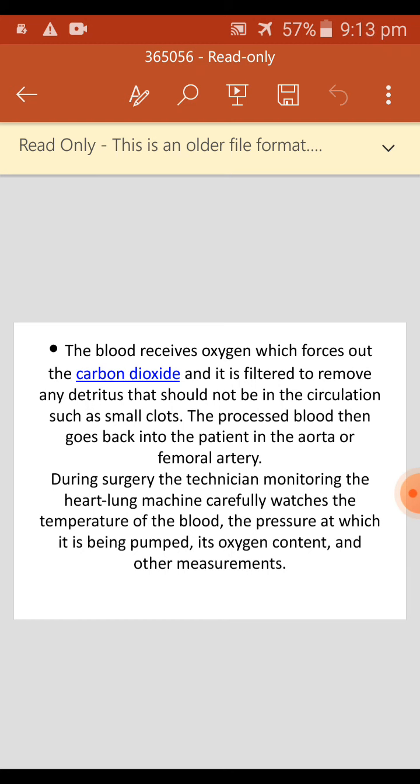Components of the heart-lung machine: the anesthetic gas vaporizer, allowing and displaying the administration of a precisely dosed amount of anesthetic gas to the oxygenator. Second one, electronic documentation system that displays and stores all relevant data during perfusion. All data are stored centrally and displayed instantly as a perfusion report, which allows for data evaluation at a later stage for statistical and scientific purposes.